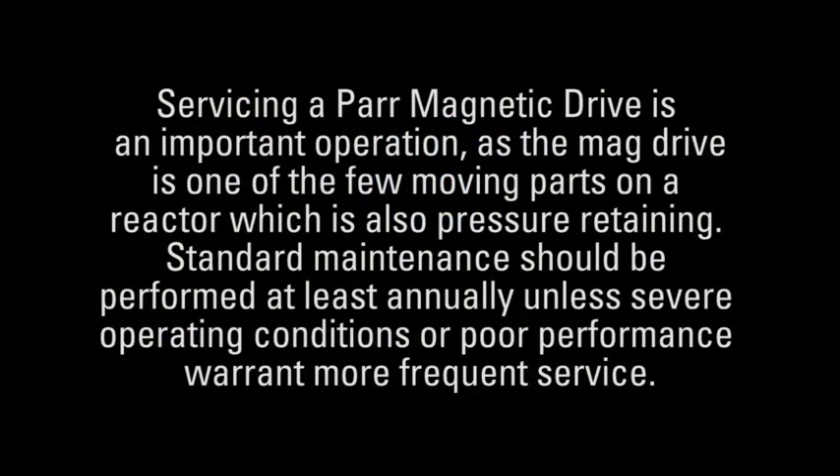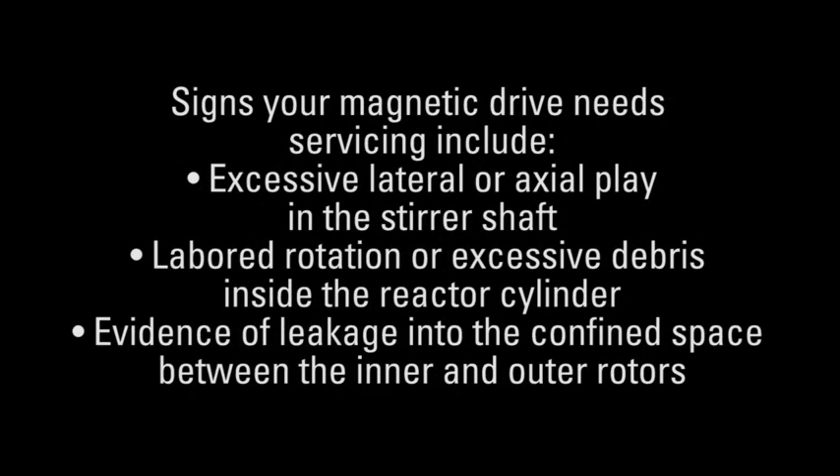Servicing a Parr mag drive is an important operation, as the mag drive is one of the few moving parts on a reactor which is also pressure retaining. Standard maintenance should be performed at least annually unless severe operating conditions or poor performance warrant more frequent service. Signs your magnetic drive needs servicing include excessive lateral or axial play in the stirrer shaft, labored rotation or excessive debris inside the reactor cylinder, or evidence of leakage into the confined space between the inner and outer rotors.